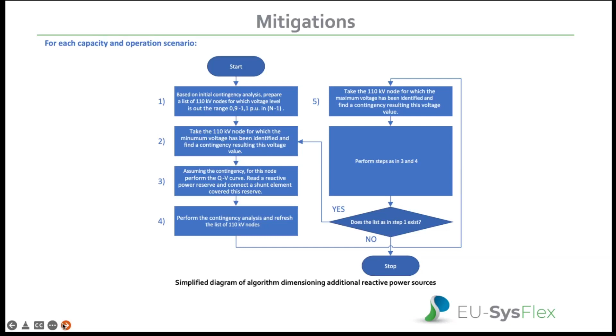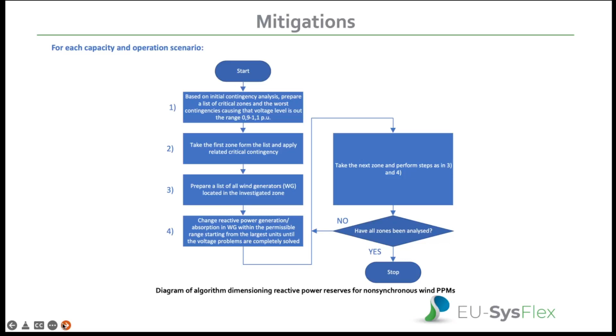For activating reactive power reserves in non-synchronous wind farms, we have proposed a similar approach, but now we analyze the vicinity of the problematic node, and we try to adjust the set points of the reactive power generation or consumption of all the close wind farms in the vicinity of that problematic node, until we find that every problem in the grid is solved. We repeat those calculations for each capacity and also for each operational scenario. So I think we can move on to the results.